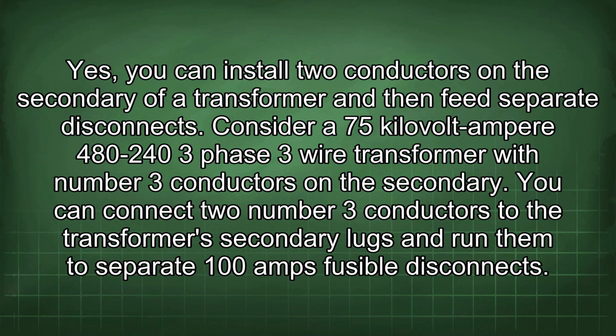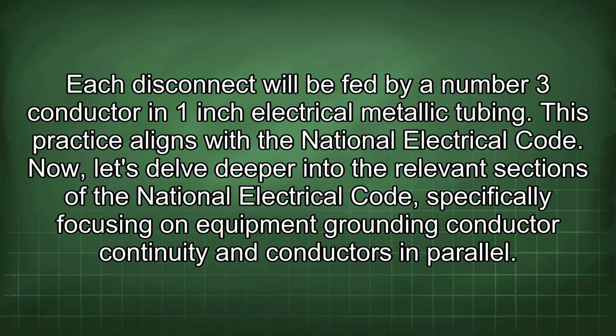Yes, you can install two conductors on the secondary of a transformer and then feed separate disconnects. Consider a 75 kVA 480-240 volt 3-phase 3-wire transformer with number 3 conductors on the secondary. You can connect two number 3 conductors to the transformer's secondary lugs and run them to separate 100 amp fusible disconnects. Each disconnect will be fed by a number 3 conductor in 1-inch electrical metallic tubing. This practice aligns with the National Electrical Code.